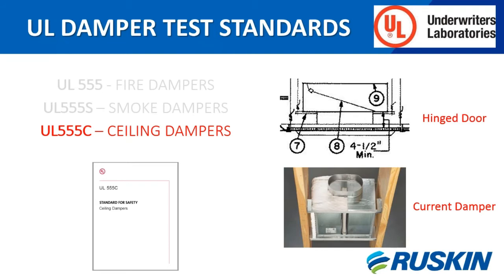The UL standard for ceiling dampers is UL 555C. This standard is used to evaluate ceiling radiation dampers for use in lieu of a hinge door type damper. The original ceiling dampers were called hinge door types because of their construction. The hinge door could vary in steel gauges but had both surfaces covered with 1/16-inch thick ceramic fiber paper and was held open with a fusible link.